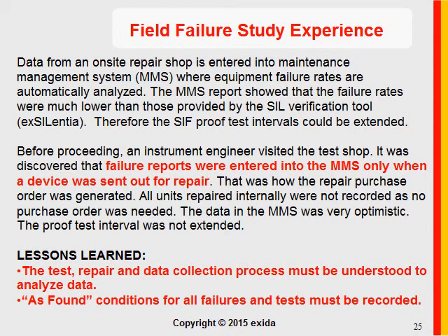However, before proceeding, a wise instrument engineer visited the test shop, and he discovered that failure reports were entered into the MMS only when a device was sent out for repair. In other words, the only units that were considered failures were those that had to be sent out, because that's how a repair order was generated.